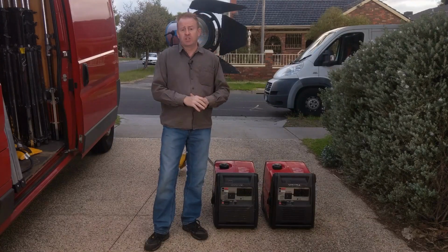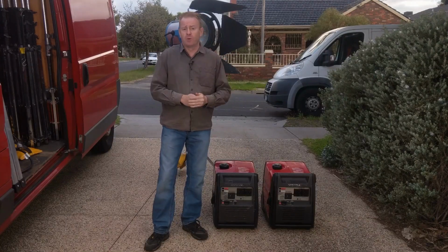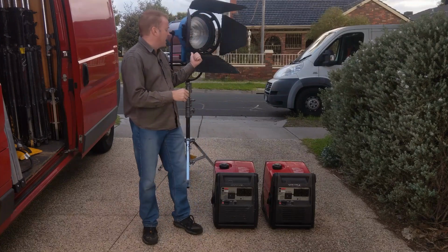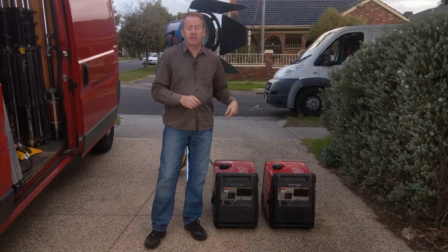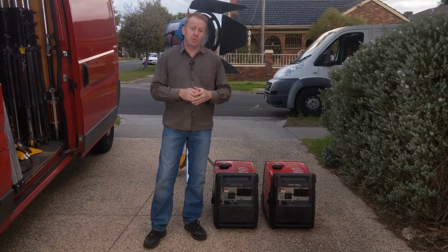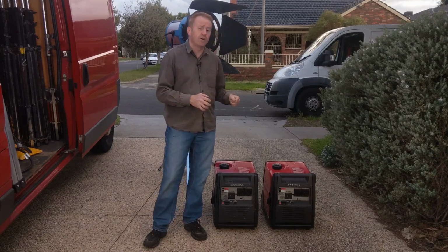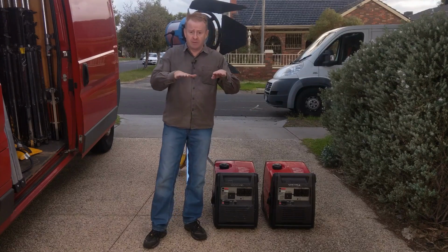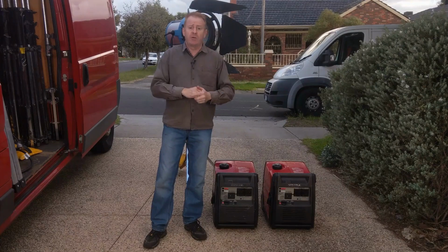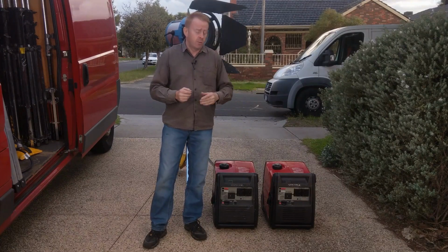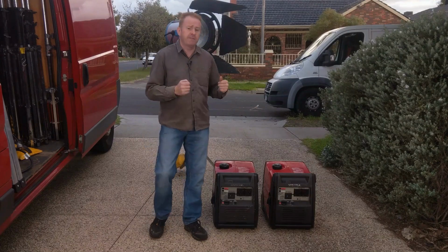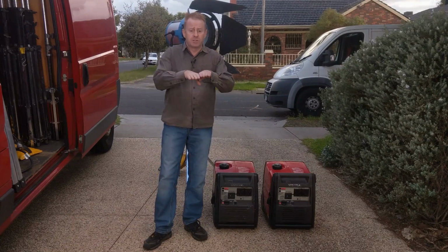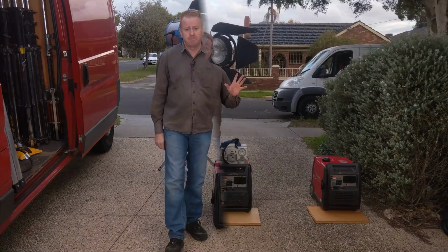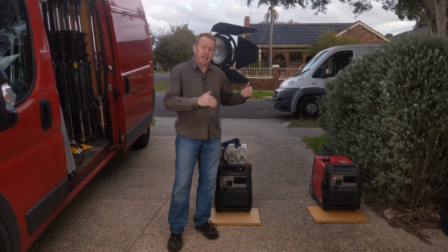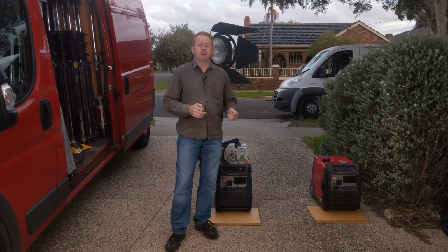All right, that was really straightforward. Now we're going to get a lot more complicated. We're going to try and run a 4K HMI off two 3 kVA generators. Now the first issue we have to deal with is these things are not fuel injected. So I'm going to have to make sure they're sitting level. Now remember earlier in the video, I said that these things suck a lot of air. Well, if I have them this close together, they're going to foul each other's air supply. So I also have to separate them. All right, now that I've got them leveled and separated, the next step is to plug in the link.